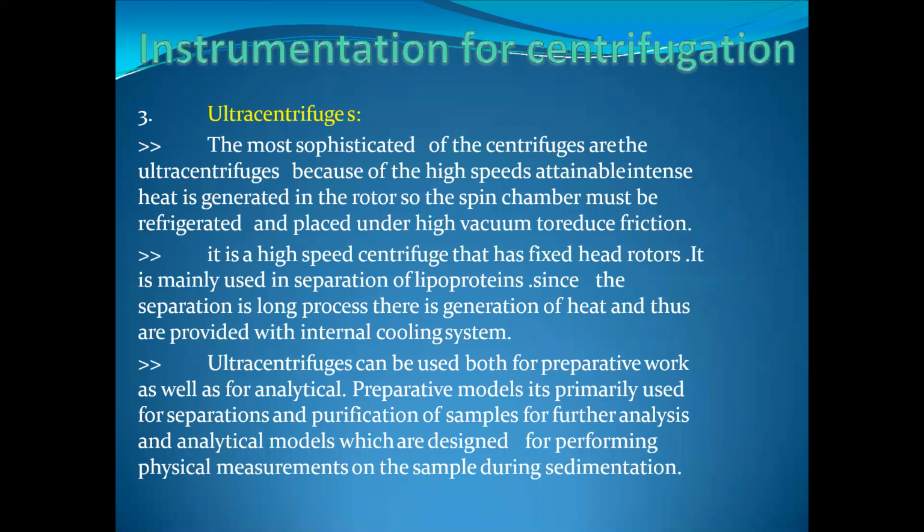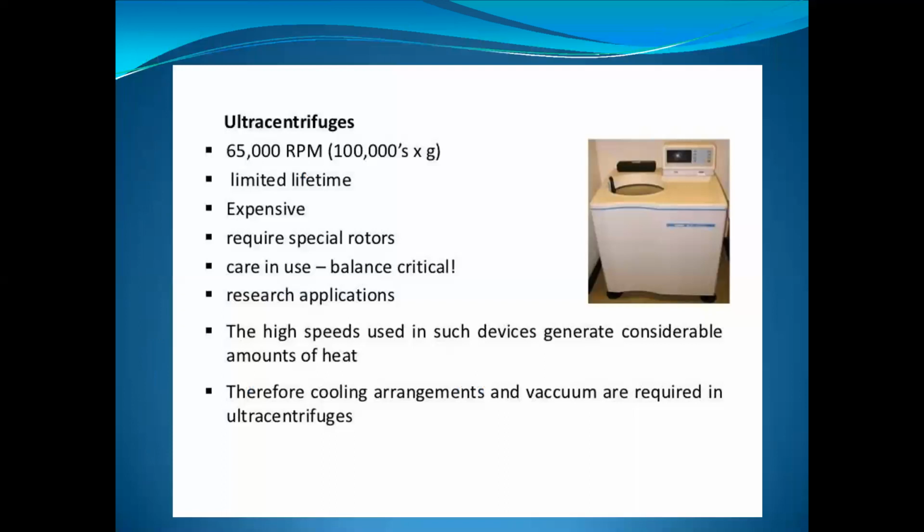Since the separation is a long process, there is a generation of heat and thus they are provided with an internal cooling system. Ultracentrifuges can be used for both preparative work as well as analytical work. Preparative models are primarily used for separation and purification of samples for further analysis, and analytical models are designed for performing physical measurements on the sample during sedimentation.